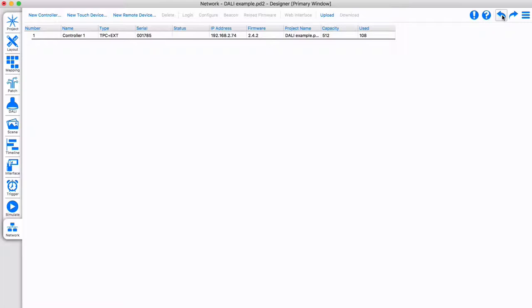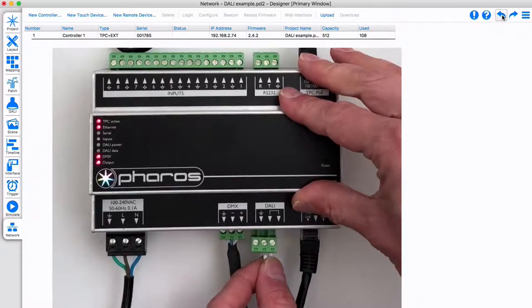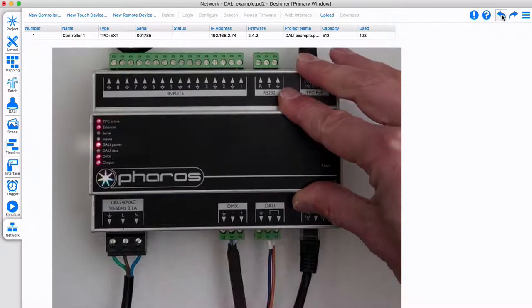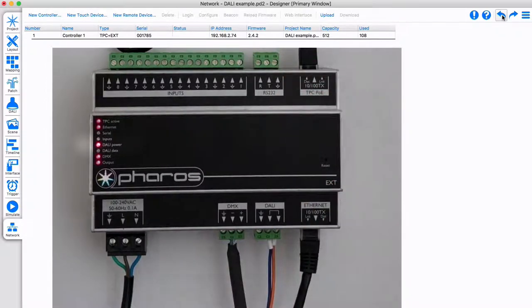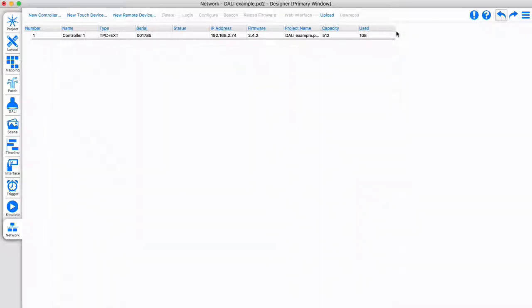Please note that Pharos DALI devices do not provide bus power. For DALI to function, you will need to ensure a correct DALI power supply is available on the bus. The DALI power LED will light up if power is present on the bus.